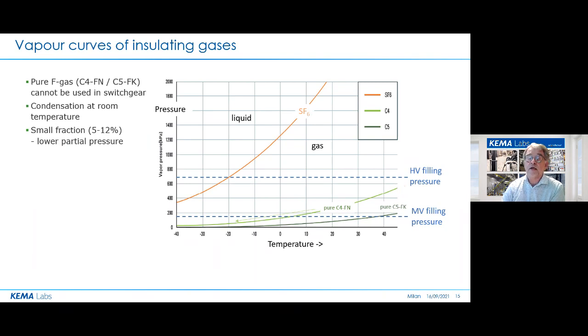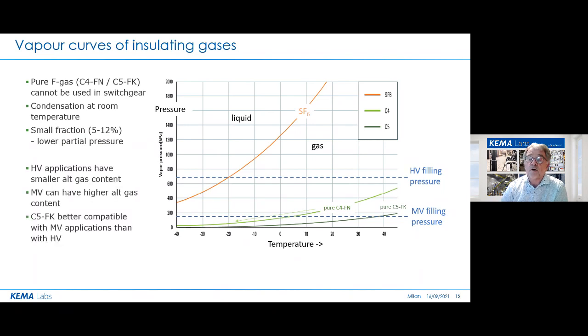Well, comparing then C5FK with C4FN, we can see that for application at lowered temperatures, C5FK, as the least volatile gas, has a bigger issue, especially in high pressure, high voltage applications. This is the reason why C5FK is ultimately abandoned as circuit breaker gas in high voltage switchgear, while it can function well in the lower pressure equipment for medium voltage. By the way, the condensation curves for natural origin gases, N2, O2, and CO2, the very volatile gases, are far beyond this range here and have no issues at all with condensation at low temperatures.